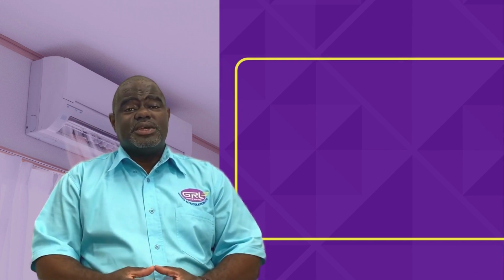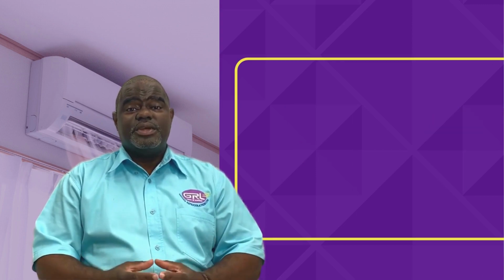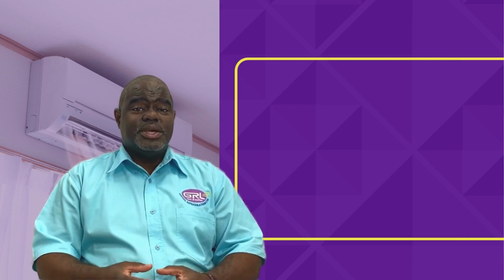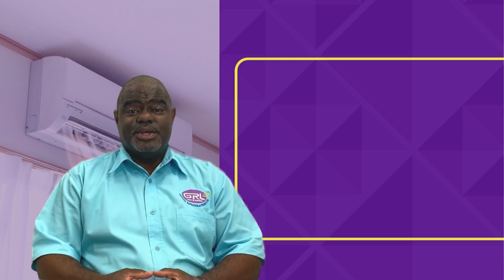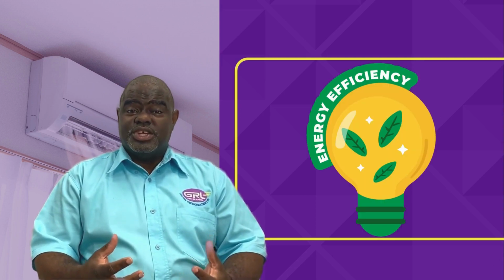An inverter AC unit is one in which the compressor can vary its outputs. What do I mean by that? Consider a light switch. It turns on and off. Now consider a dimmer switch in which the brightness can be adjusted quarter, half, 75%, full brightness. An inverter compressor can vary its output with respect to the cooling demand that is needed at the time. This is why these units are more energy efficient.